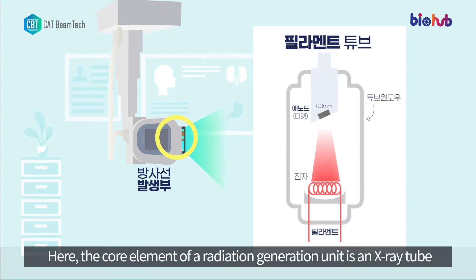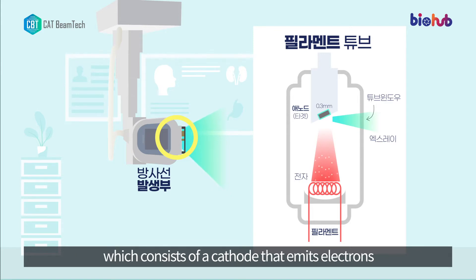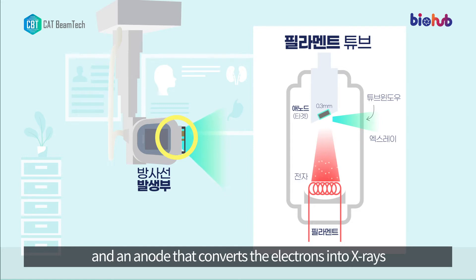The core element of a radiation generation unit is an X-ray tube, which consists of a cathode that emits electrons and an anode that converts the electrons into X-rays.